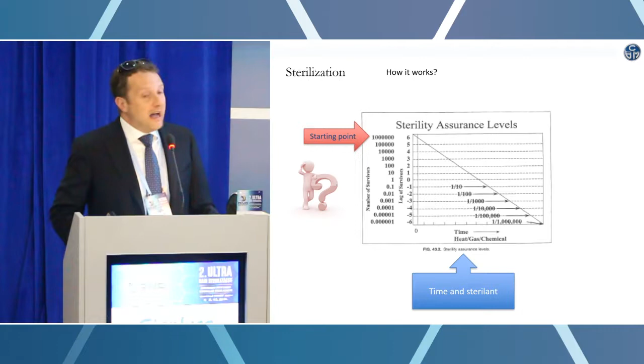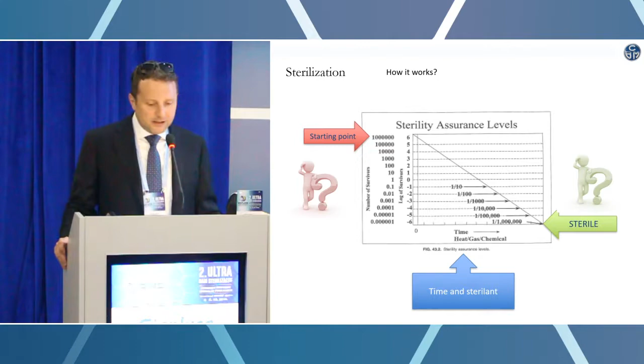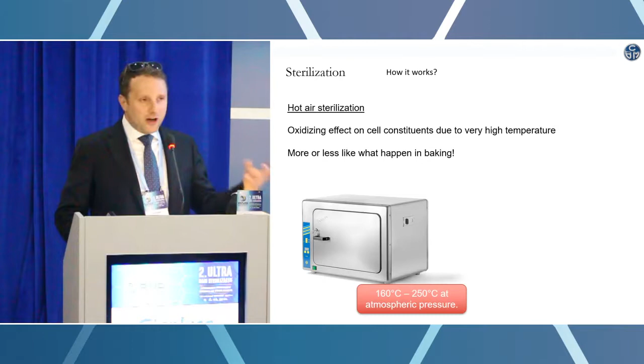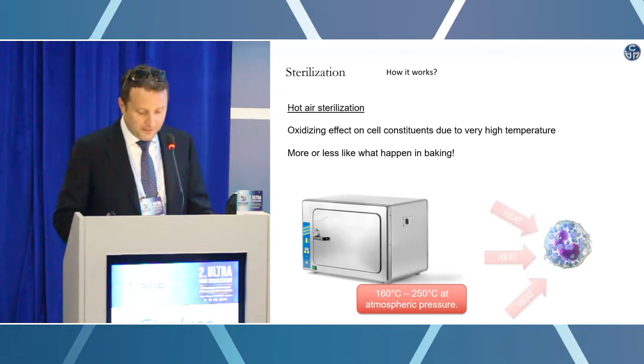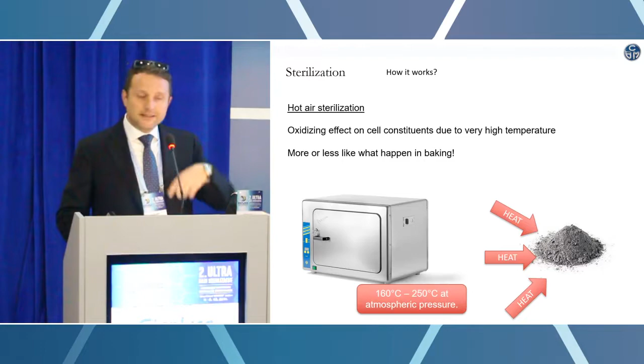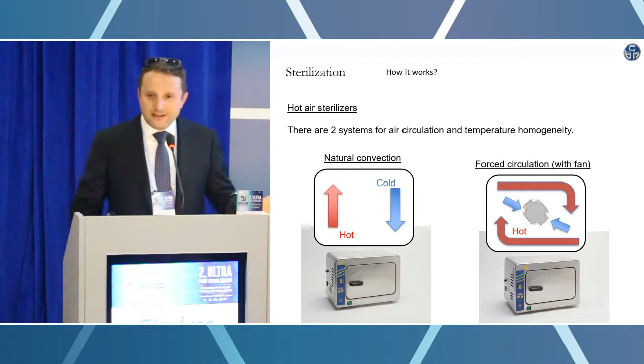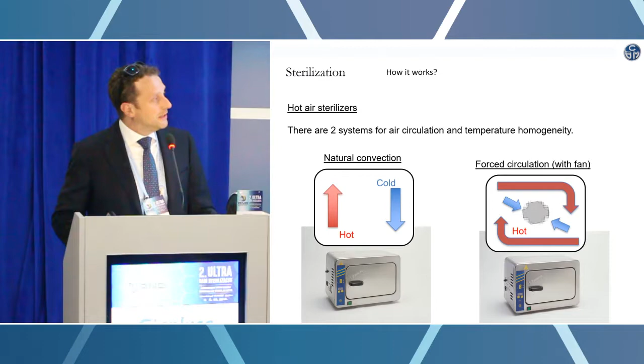How does hot air sterilization work? It is quite commonly still used, especially in small cabinets or the dental field. This effect is obtained by oxidizing the cell constituents by means of adding heat, more or less what happens in your domestic oven. We simply destroy all the cells. It works at a very high temperature, from 160 to 250 degrees, at atmospheric pressure. Hot air sterilizers on the market can be of two different types depending on the circulation of the heat inside the chamber. As in the kitchen, we can have a natural convection sterilizer, where there is a natural circulation of air, or we can have a fan that forces the circulation of the heat inside the apparatus.